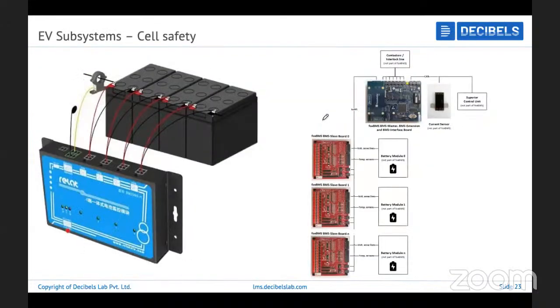So for that, we have a system like this, which is called the battery management system. You have units that measure the voltage of the cell, and a device that measures the current of the cell, the current of the battery pack. If the current drawn is more than a specific value, the BMS will shut down the battery or disconnect it from the load.